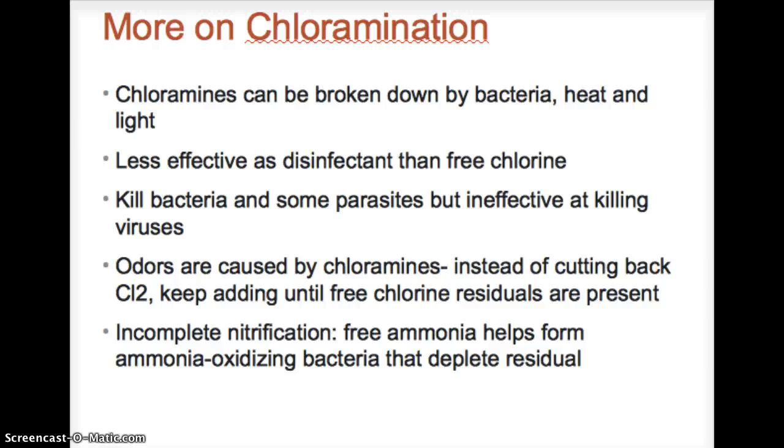Instead of cutting back the chlorine, keep adding free chlorine until free chlorine residuals are present. And that's a little bit counterintuitive, because once you get that chlorine odor, you think, well, I should stop adding chlorine, but you really should add chlorine until there are free chlorine residuals present once again.